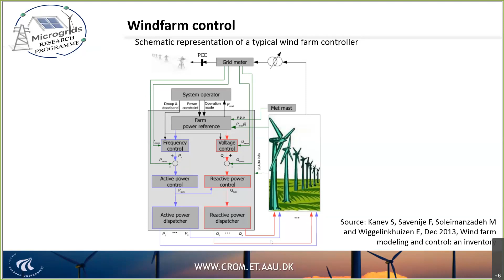And here you have voltage and reactive power with those blocks with frequency control. Then we have another block of active and reactive power controllers that is sent to each of the wind turbines by means of these active and reactive power dispatchers. So you calculate how much is active and reactive power, adjust according to frequency and voltages and according to how much the system operator requests, and then distribute those dispatch signals. You can see here we have again a wind farm hierarchical control.